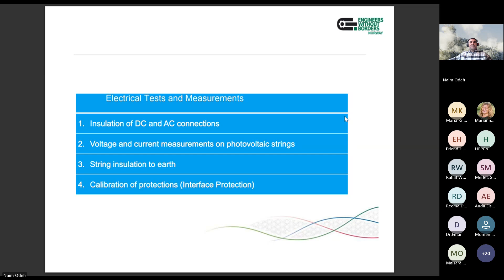Yeah. So this is the first test, which is the insulation of LVDC and AC connections. So insulation is very important. Doing an insulation test gives us an indication about the system, about the connections, if there is any leakage, if there is any scratch or touch of the cable anywhere.